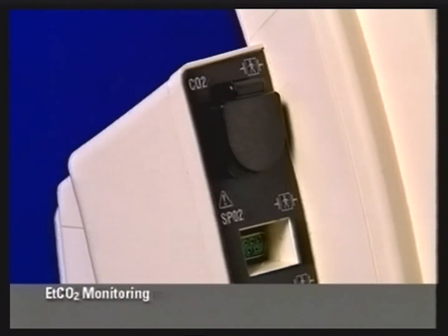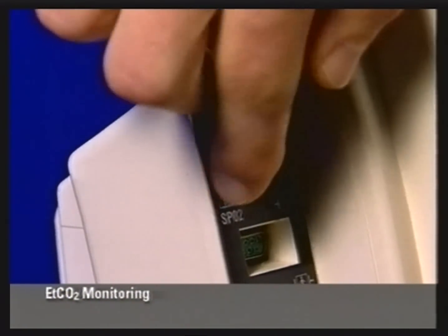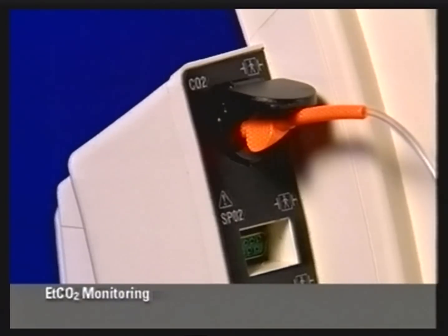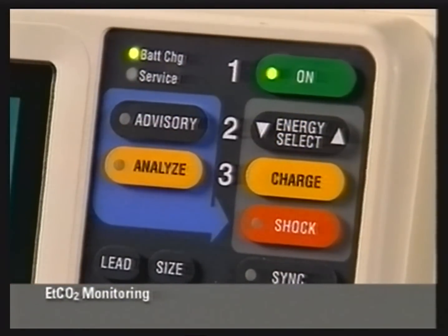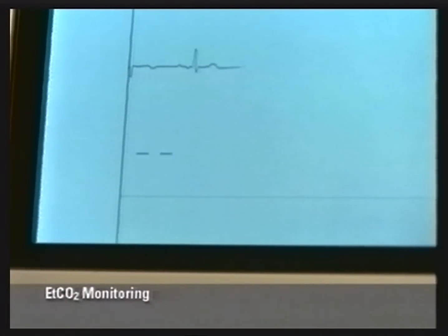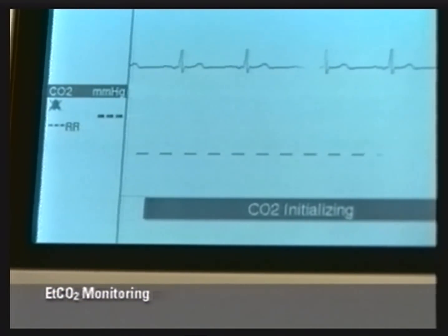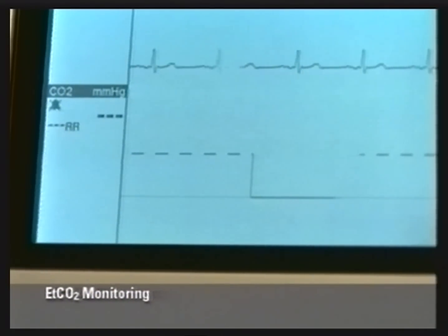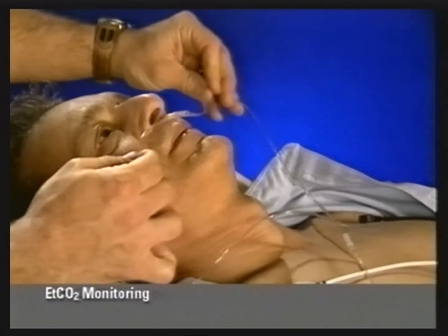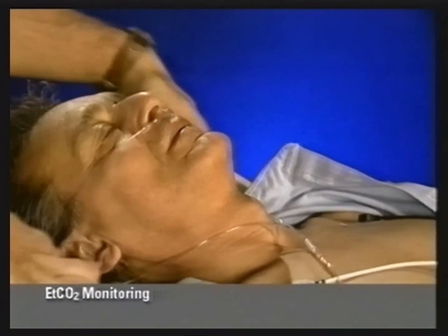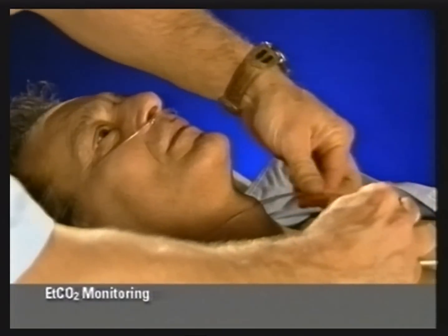To monitor end-tidal CO2, connect the nasal filter line tubing to the CO2 tubing connector. Insert the filter line connector and turn the filter line wings just until some resistance is felt. Power on the monitor and adjust contrast if necessary. The CO2 monitor senses when the filter line is connected and begins initializing immediately. This initialization warm-up includes a self-test and auto zero and may take up to 2.5 minutes. Apply the nasal end of the filter line to the patient with the prongs curving downward and secure the tubing by sliding the sleeve up toward the chin.